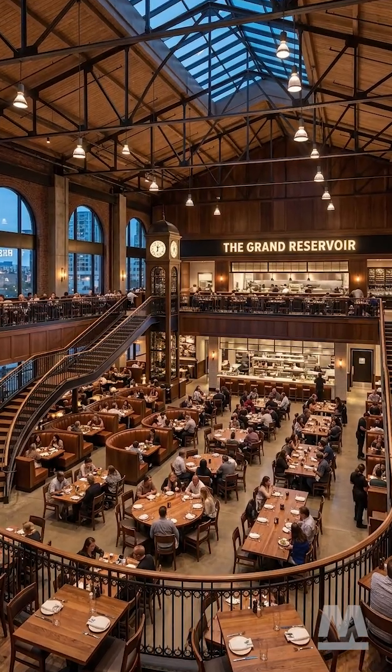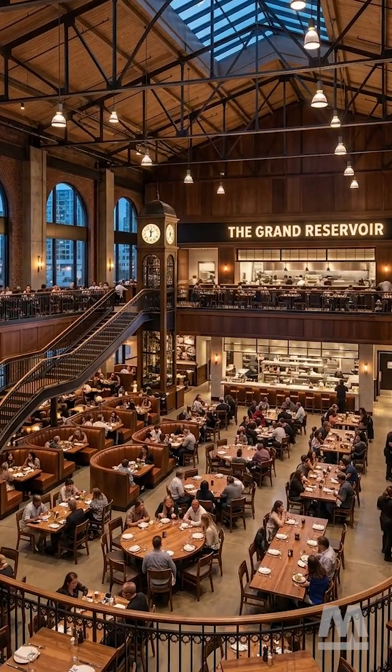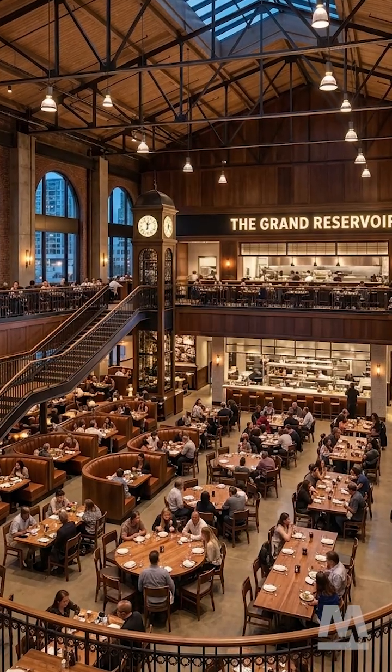Yeah, 907 basically takes the various occupancies that we covered when we went over chapter 3, and it picks out the occupancies that require a fire alarm system, and it tells you how much fire alarm system is required based on either the occupancy or in some cases the number of occupants within the occupancy. For example, an assembly occupancy, which could be a restaurant, has an occupant load requirement of 300 or more people. So if you've got seating for 300 people, or you get 300 people into your building, then you require a fire alarm system. But if you have a larger facility and you're over 1,000, then that changes the requirement from a simple fire alarm system to an emergency voice evacuation system.